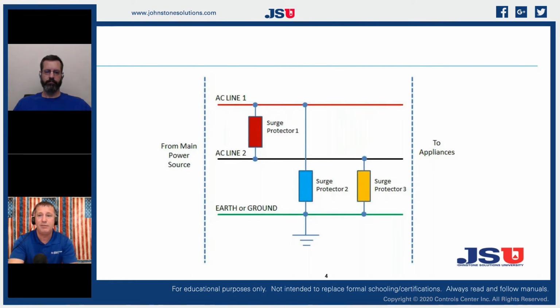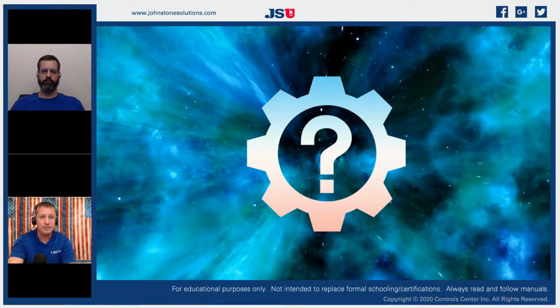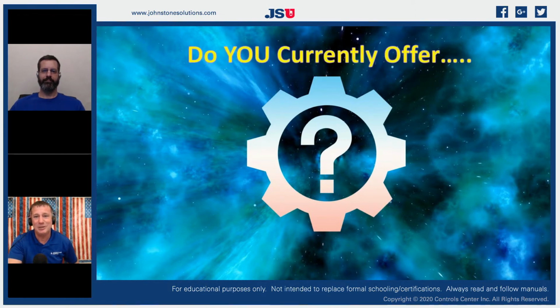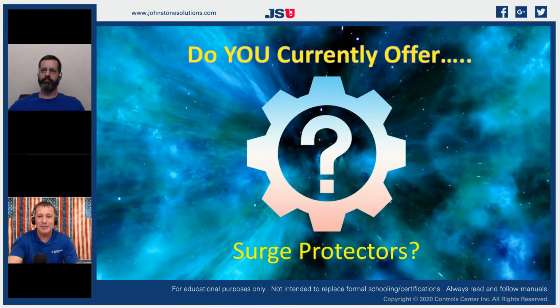So it's a dual part device, and it has a lot of opportunities for our equipment, because when we look at the benefit of a steady voltage going into a circuit, well, we don't always have the most steady power supply coming from our lines, do we? So just as a quick poll, I wanted to make a poll here. As a contractor, do you currently offer surge protectors? Let me open up my polls here real quick. Does anyone offer surge protectors for either your outdoor units or your indoor units while you're doing installations? I know you, Paul, you brought this up before, using surge protectors, especially for indoor units, air handlers and furnaces.